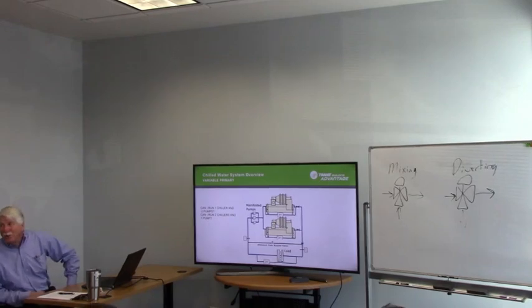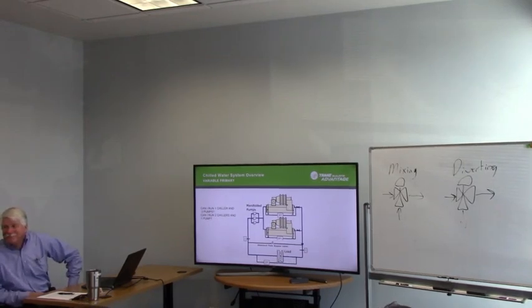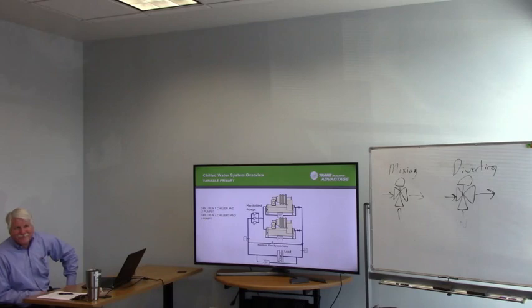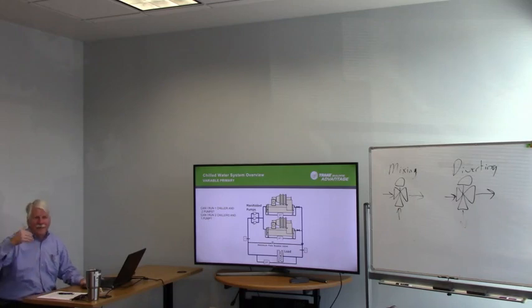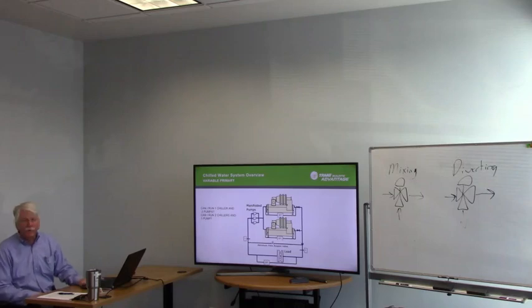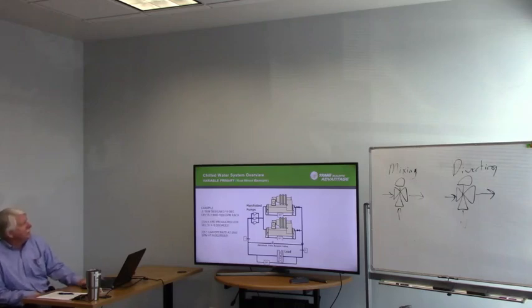Can I run two chillers and one pump? As long as that pump is inside the minimum flow on both chillers. Maybe, yeah. So the reason I bring this up is, it's not that you always have to do this to either one of those. Okay?